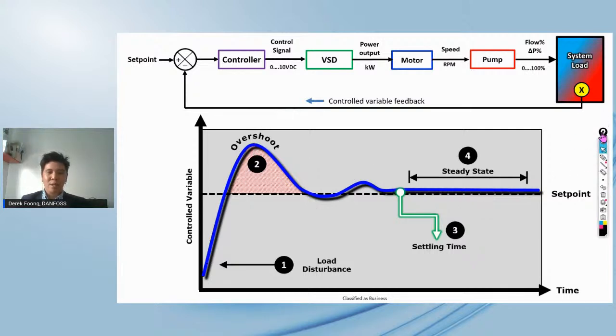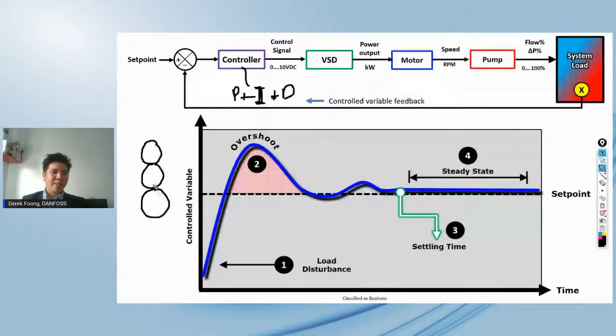That calls for a lot of expertise from the field to actually tune the PID, that is, the proportional band, integral time, and derivative time in the controller. Of course, it is usually trial and error tuning. If not, we could employ Ziegler-Nichols or Tyreus-Luyben tuning techniques. But bear in mind that tuning PIDs is like putting three bowling balls vertically together. Imagine these are bowling balls; PID is like balancing them vertically. If we are not tuning it well, it could fall out of balance. All right, so now let's move to the next topic.